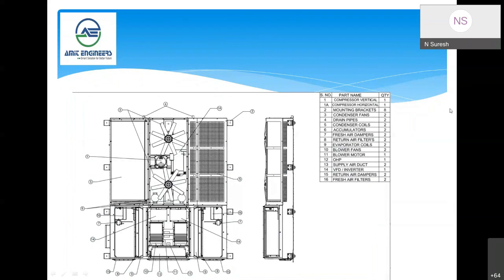Yeah, this is the overall arrangement of the components in the air conditioning system. As I briefed earlier, there are two compressors. This is a vertical compressor and the other one is a horizontal compressor. And there are 8 mountings. These are most important during installation. We are supplying anti-vibration mounting pads with 10 mm plates that will be installed first on the coach, and the unit will be mounted on the anti-vibration pad.